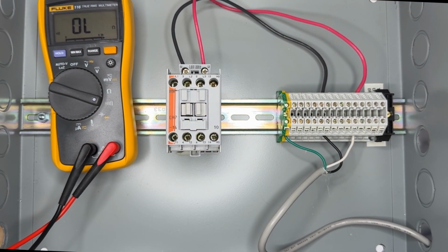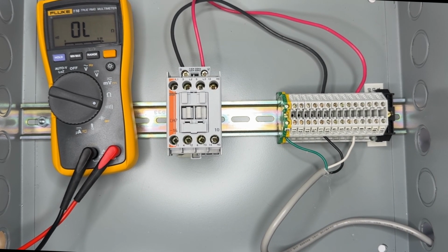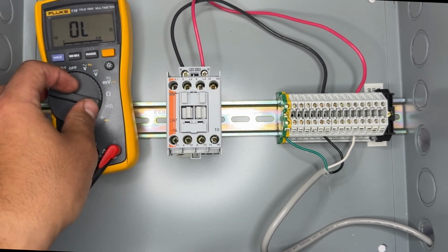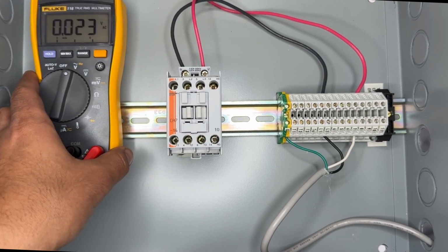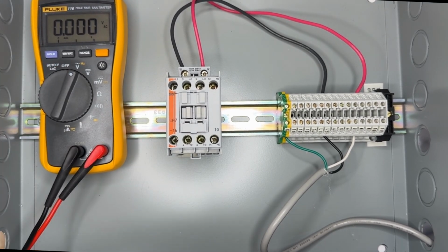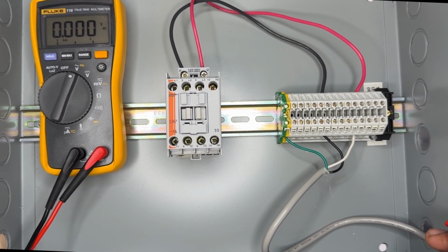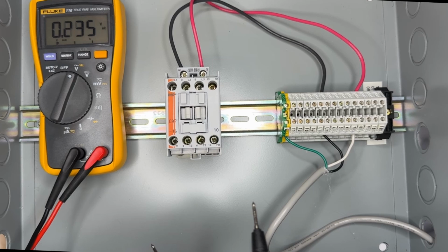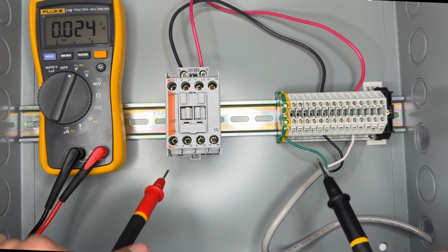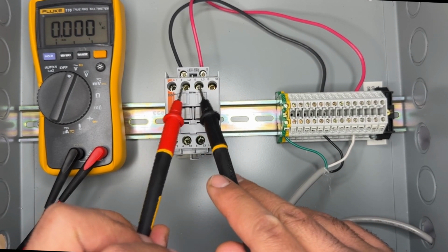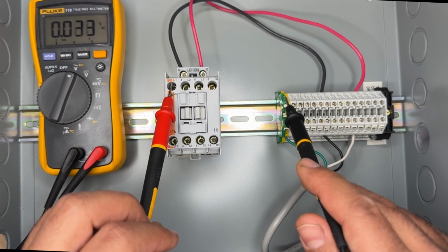So now for the next test, you can test the contacts when you're live. So I'm going to get the coil powered up and the plunger to pull in there. So now you want to set your multimeter to volts. AC is most likely what you're using, but that'll depend on your application. And now what you want to check is phase to phase across each of the 2 phases, or phase to ground.